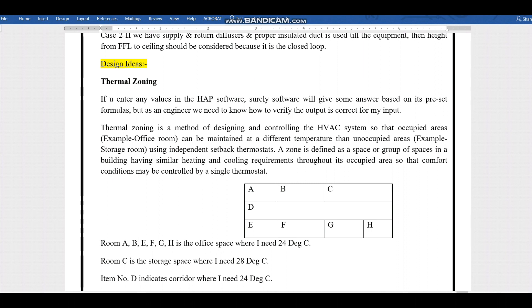As I mentioned earlier, if we enter any value in the HAP software, the software will use some assumptions. As an engineer, you need to know how to verify that. Thermal zoning is a method of designing and controlling the HVAC system so that occupied areas can be maintained at a different temperature than unoccupied areas.